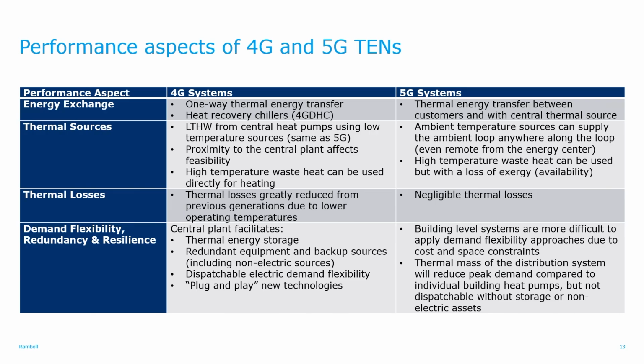Demand flexibility is the ability to reduce electrical demand for the grid. With a central plant, it's easy to dispatch electrical demand flexibility because of the thermal energy storage and the non-electric sources as backup or peaking.